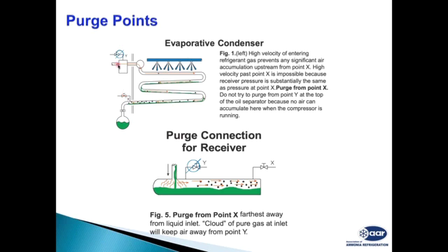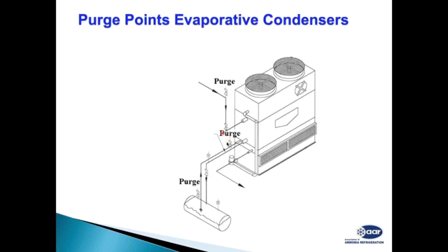What happens here is, when this ammonia gas and the air both come into the condenser, if you can see, now here we have both gas and air. But as we go down, at the end of the condenser, whatever ammonia gas is there becomes liquid, and what is accumulated is the air. So this foul gas, as we call it, we have to tap at the outlet of the condenser. Different applications: this is a manual purge point for the evaporative condenser. These are the purge points for the automatic purging system.